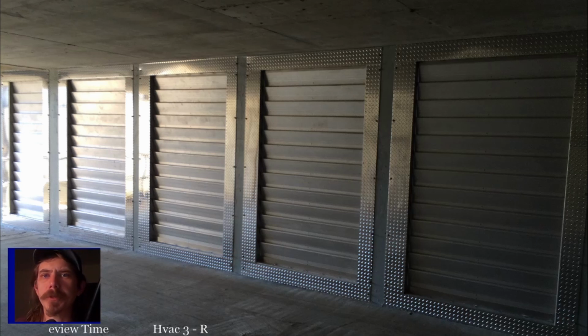So variable frequency drives, let me check what we've got to go over. All right. On variable frequency drives, if you remember from our class on it, its purpose is to control the speed of the motor. Generally it's going to be used in blower motor situations and in head pressure controls. That's your most common applications. Doesn't mean it's the only applications, but your most common applications.